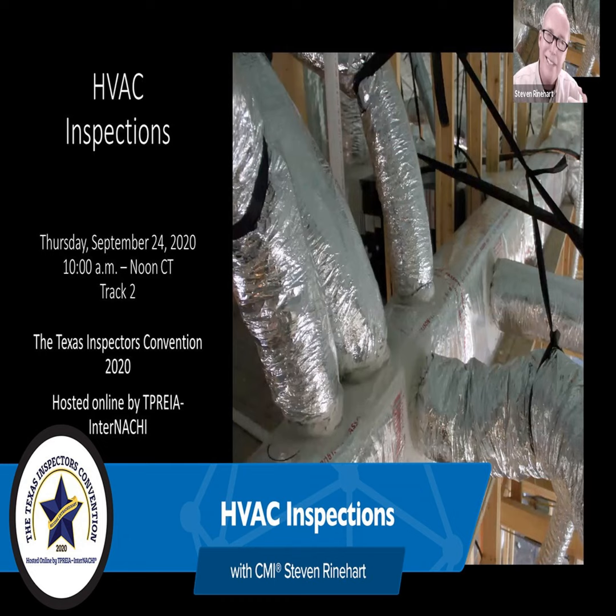The actual wording makes it look like the vent portion of a drain, which is above all the fixtures, and might make you think that anything below that might be okay because it's a wet drain anyway. But there's too many scenarios where that plumbing can get clogged up and condensation does not stop. It's like a condensation pump. I didn't talk about that. Condensation pumps. If you see one, make a note of it.